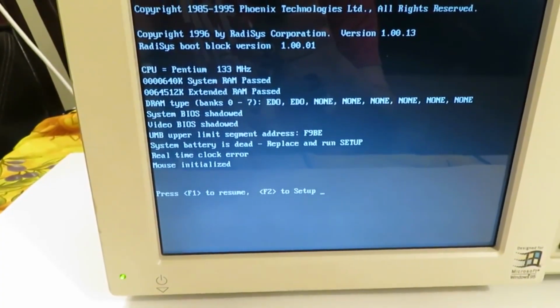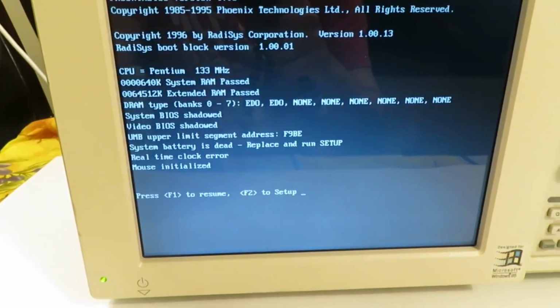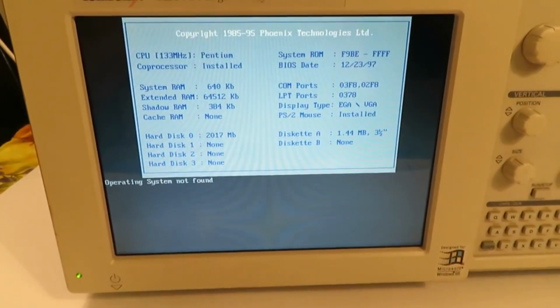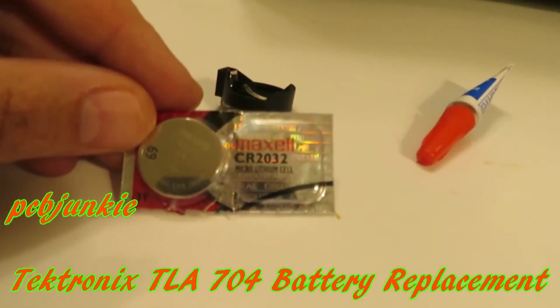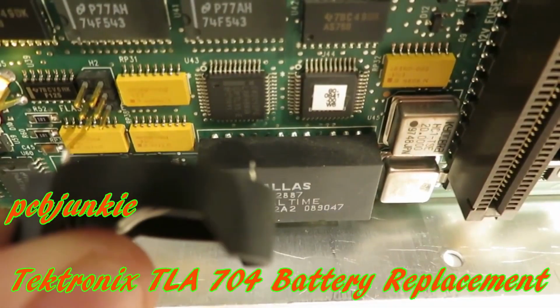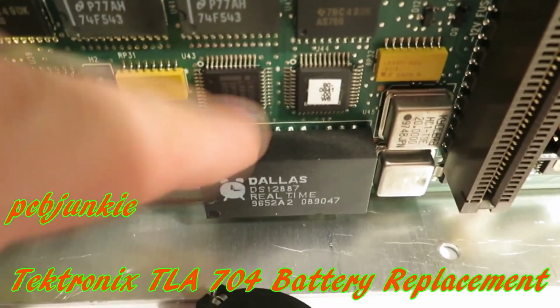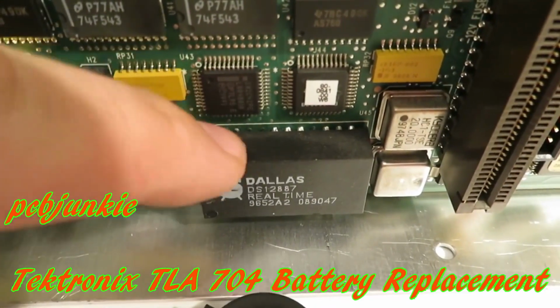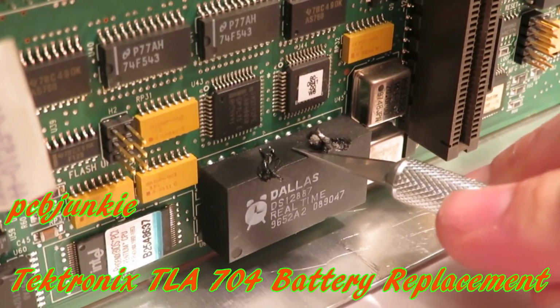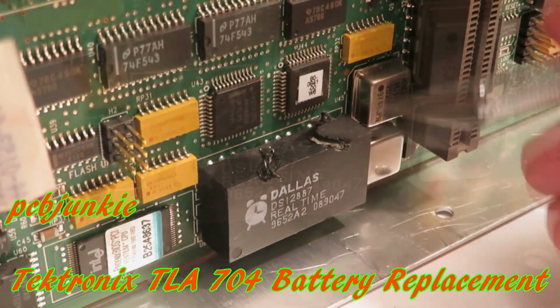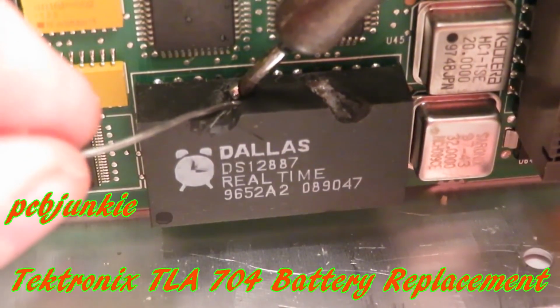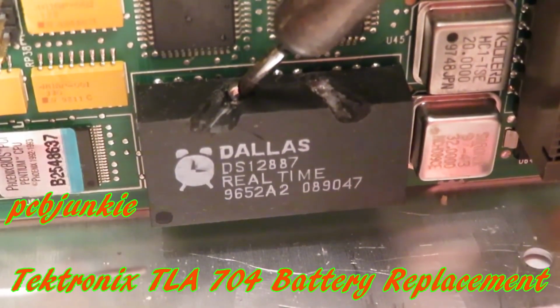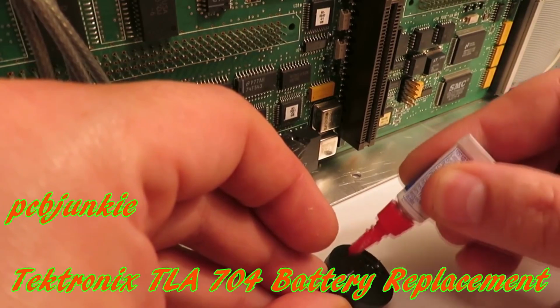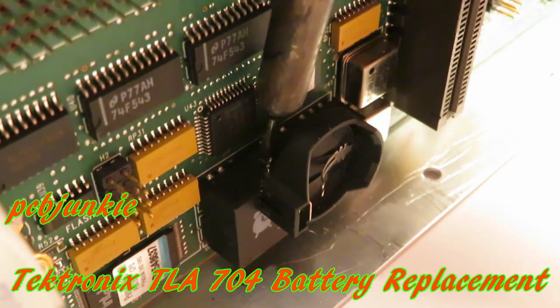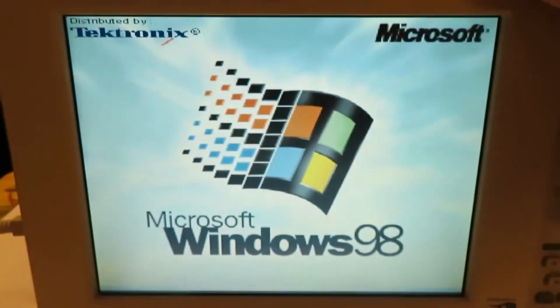Now I'd also like to thank a chap that runs a YouTube channel called pcbjunkie, and I'm afraid I don't know what his name is, but we've had again an exchange of quite a bit of information, because we thought the original problem was the real-time clock inside this piece of equipment, because it has, I don't know if it's a Dallas real-time clock. It's got a little black brick module, and that fails commonly, and apparently if that backup battery fails in the real-time clock, it loses some of the memory settings, the BIOS settings, and the equipment won't boot. So if you have got one of these pieces of equipment and it just won't boot, it's quite likely that's a problem.